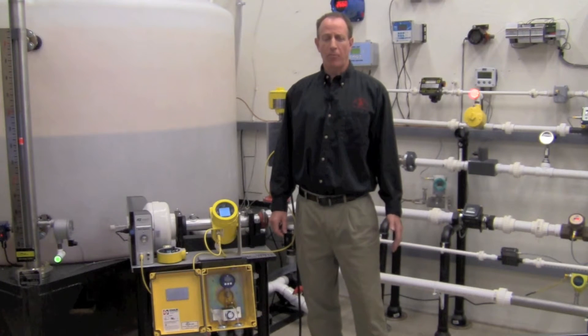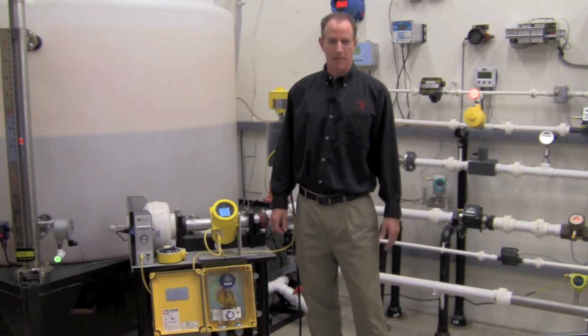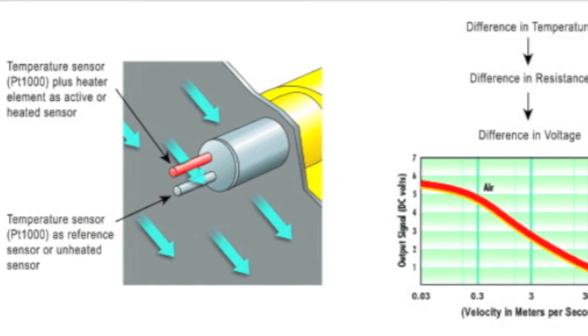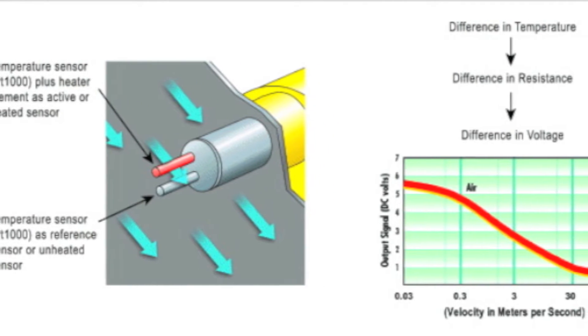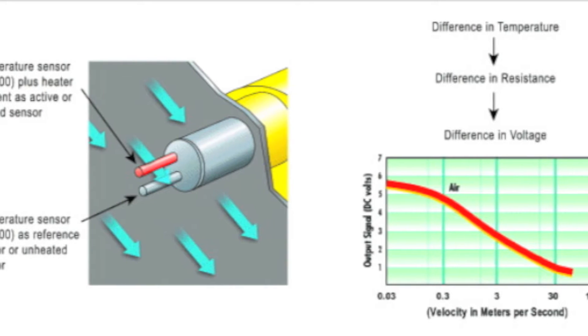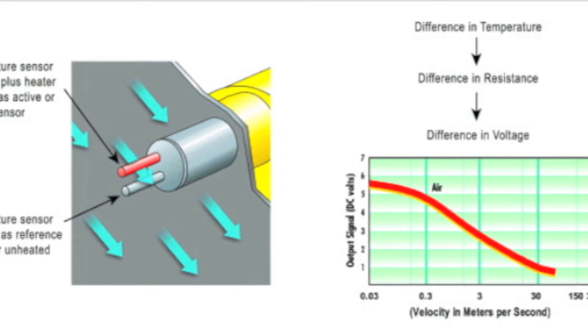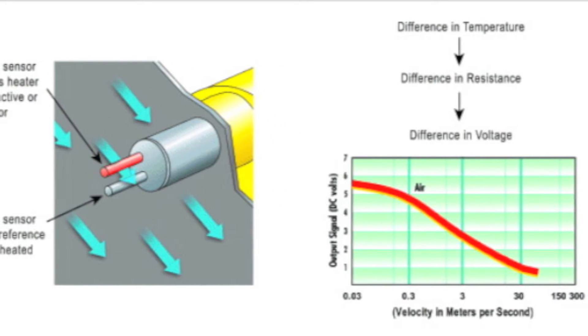The ST100 flow meters operate on the principle of thermal dispersion. The circuitry measures the temperature difference between the heated and non-heated sensors. The greater the mass flow rate, the less temperature difference between the two sensors.